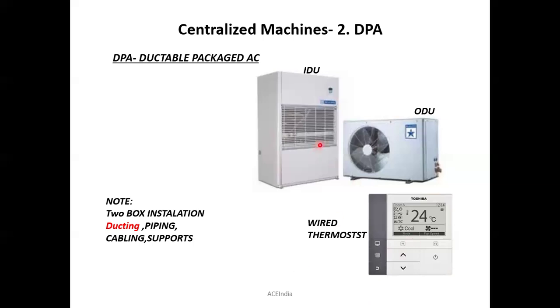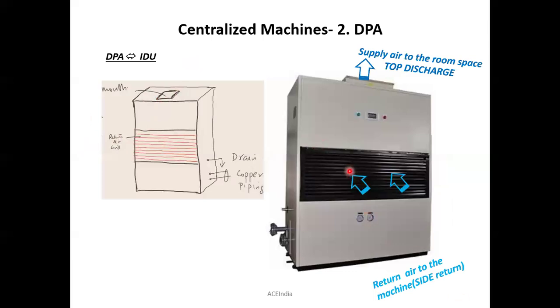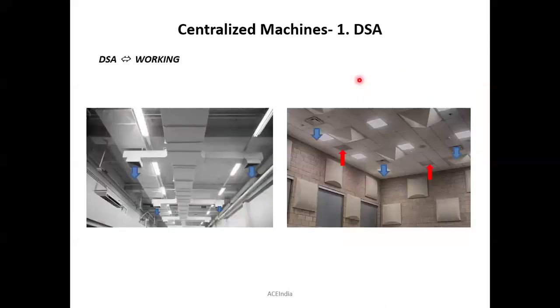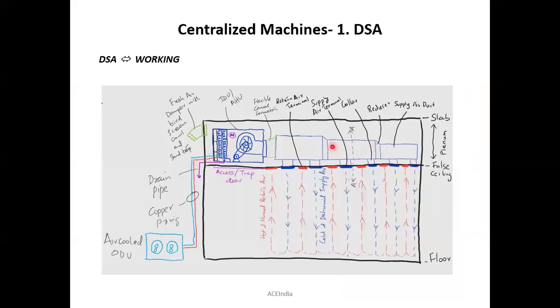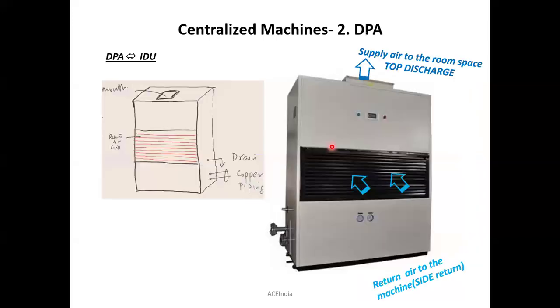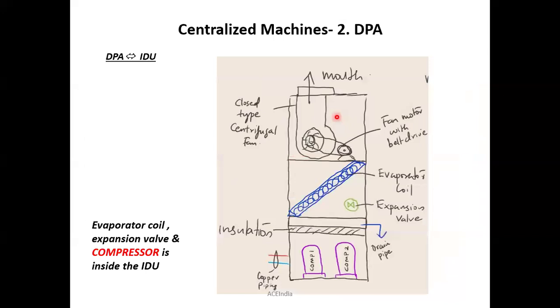Okay, now we can see the working of this one. Here you can see this portion is termed the return air grill of the DPA machine. So this is an individual DPA machine right here. And the DPA machine has a top discharge mechanism. But you can see that the DSA is a side discharge mechanism. That means the air is thrown sideways. But in the case of DPA, the air is discharged from the top. So that's why we use a connection called a plenum box. We can learn that right now.